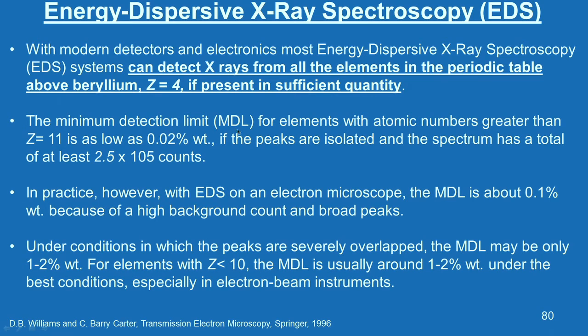The minimum detection limit (MDL) for elements with atomic numbers greater than 11 is as low as 0.02 weight percent, if the peaks are isolated and the spectrum has a total of at least 2.5 × 10⁵ counts. In practice, however, with EDS on an electron microscope the MDL is about 0.1 to 1 weight percent because of high background count and broad peaks. Under conditions where peaks are severely overlapped, the MDL may be only 1 to 2 weight percent; for elements with atomic number less than 10, the MDL is usually around 1 to 2 weight percent under the best conditions.